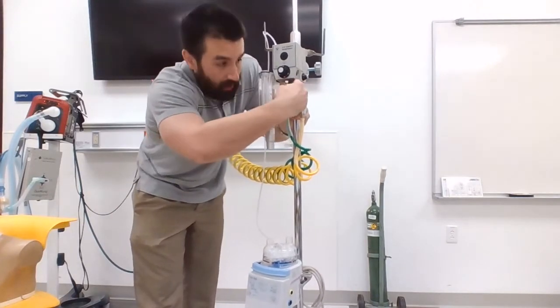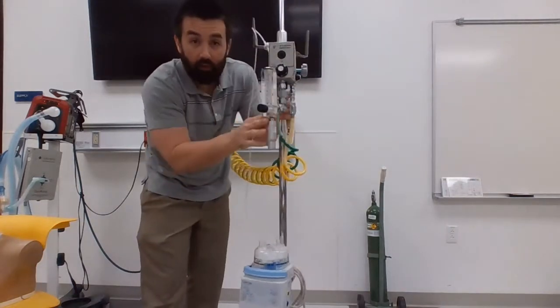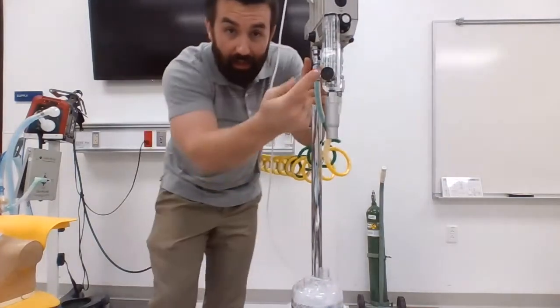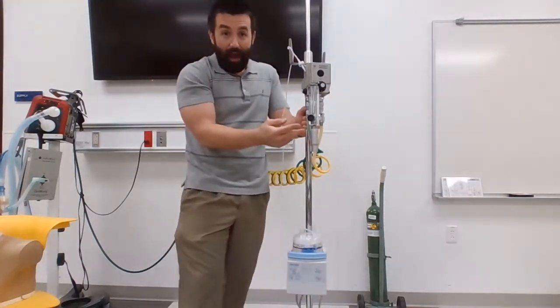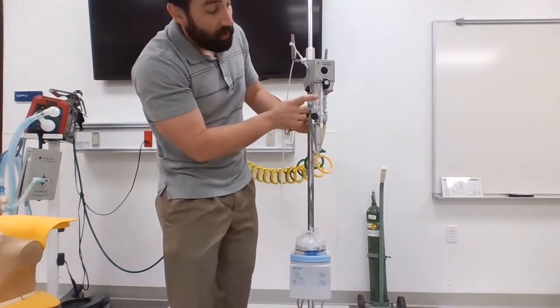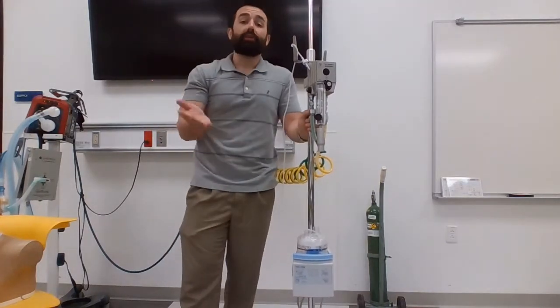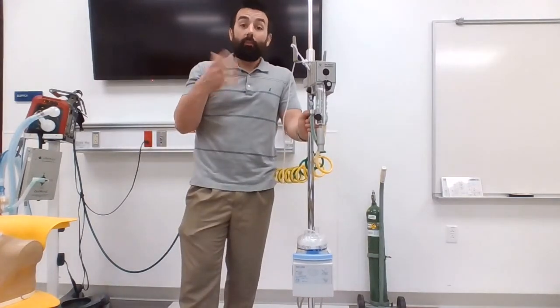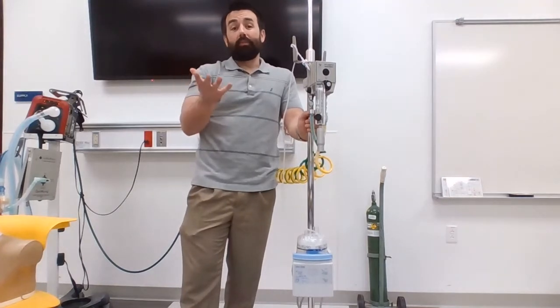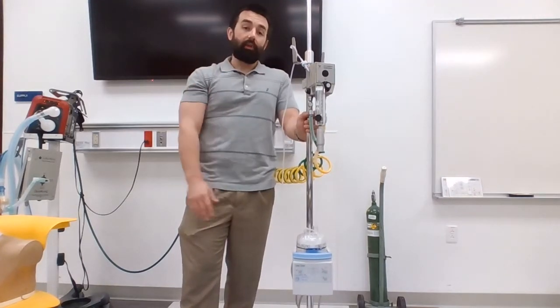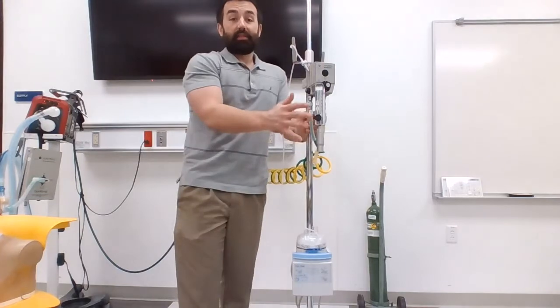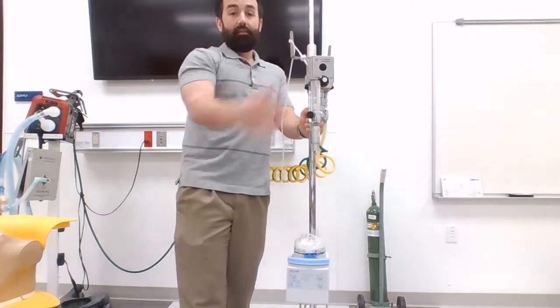What I have here is a couple of other fittings, and I had this hooked to a high flow meter. So you can't really see very well in this video, but my high flow meter goes up to 75 liters a minute. Traditionally in practice, we're not going to go up that high. We'd maybe go to 60, and that would be the uppermost limit. But this gives us the ability to set flow and FiO2 separately.